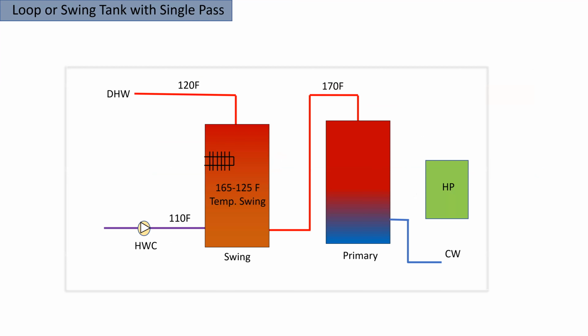I want to touch on what we call a loop or swing tank with single pass. This is really important because it plays into load shift as well as maintaining efficiency with single-pass devices. The concept: we've got a heat pump, and a primary storage tank sized for your peak draw, which happens—I'll show you a profile—usually in the morning rush and in the evening.